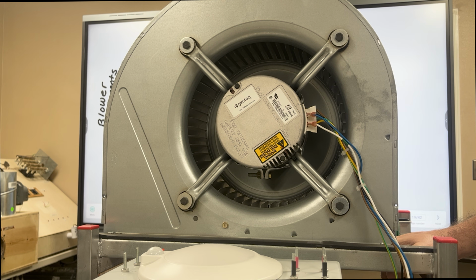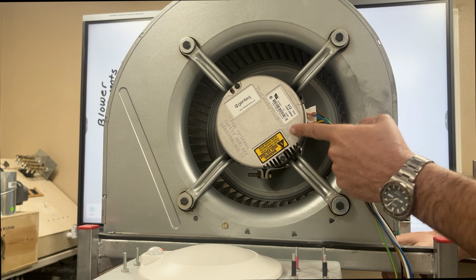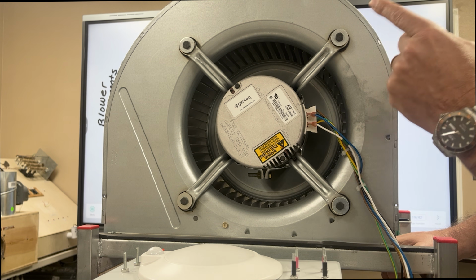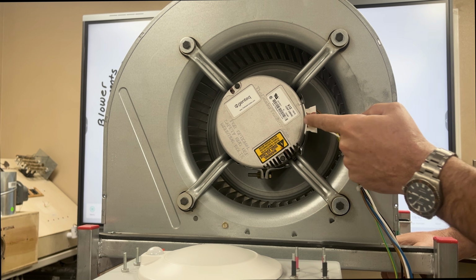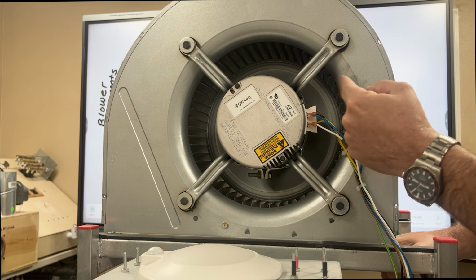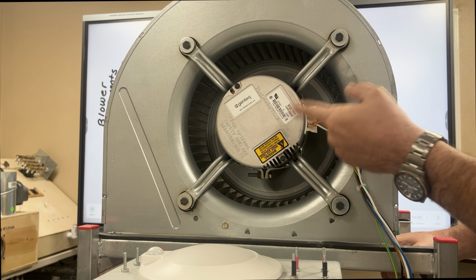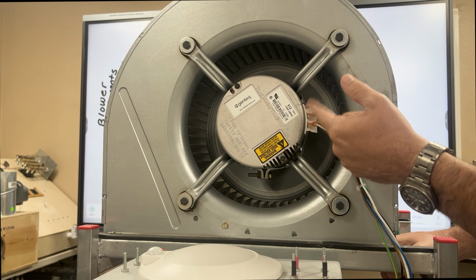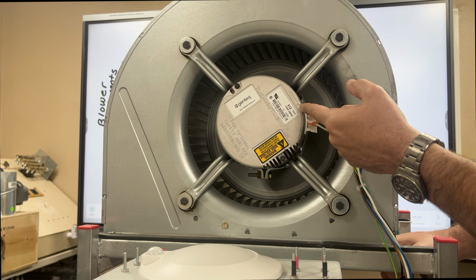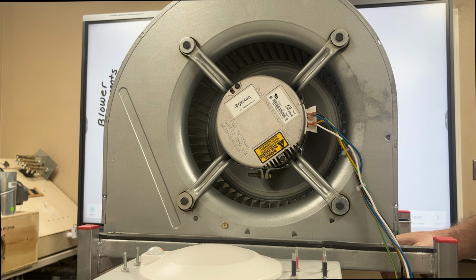This is a pretty neat motor because on the PSCs you had to integrate a capacitor and a relay to get it to come on. Well, these motors have modules on the back side of them, and inside these modules there are already capacitors and relays. As a matter of fact, when this motor gets the call for another speed, it will drop out one speed and pick up the next speed, so it will increase its speed if we apply 24 volts to another speed tap. I'm going to show you that too. And hopefully that helps illustrate when you have a call for a second stage, how this motor ramps up, and when you lose that call for a second stage, how it ramps down.